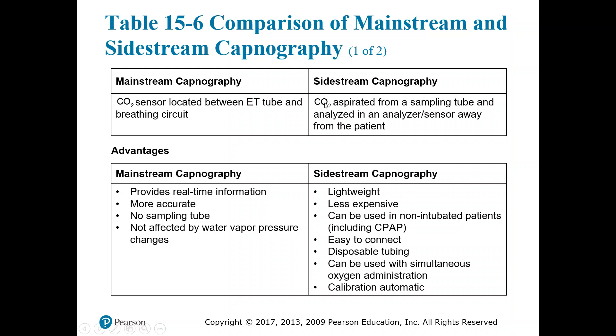With sidestream, it takes a sample of the gas through a sampling tube and analyzes it in an analyzer away from the patient, so there's some dead space in that line. Sidestream capnography is generally lightweight and usually combined with another monitor you're carrying anyway. They're less expensive and can be used in non-intubated patients, including with CPAP, by use of either the nasal cannula or the ET tube adapter. It's easy to connect — just a simple slip-in and twist into your monitor. The tubing is disposable, can be used with simultaneous oxygen administration, and the calibration is automatic.